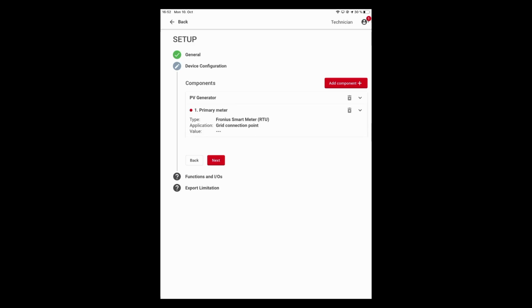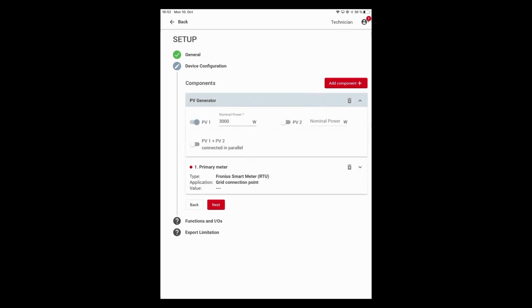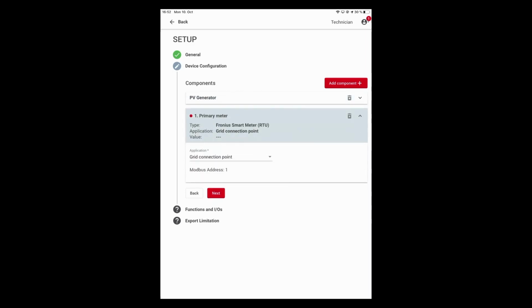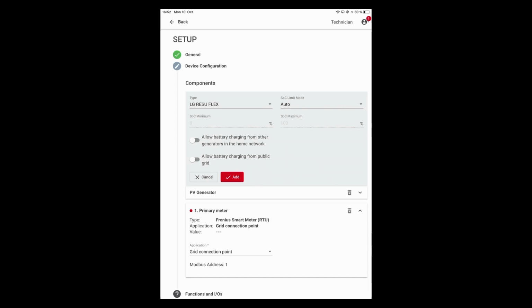Yeah, then we can add components here, and as you can see now we have a PV generator, so we can add the nominal power of the PV generator installed to the inverter. We can add a very important Fronius primary meter that we need for our battery system, so we need to add the primary meter here. And third, you can then add a component and just add the battery system here from the list. Yeah, and then you can choose from this list which battery system you want to add. In our case we are choosing the LG RESU FLEX.